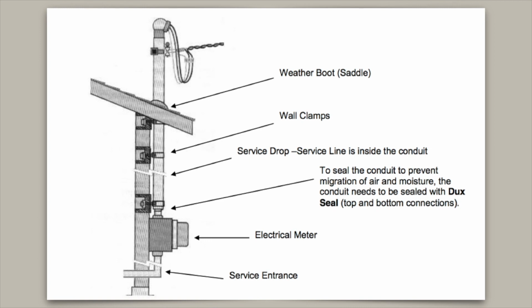The overhead service supply will be attached to the house in many ways. Usually, the wires are attached to a mast. Older homes will have a wooden or steel angle mast running down through the roof of the home. When checking this type of service, be sure to check the point of attachment. If this is loose, it could cause some problems.